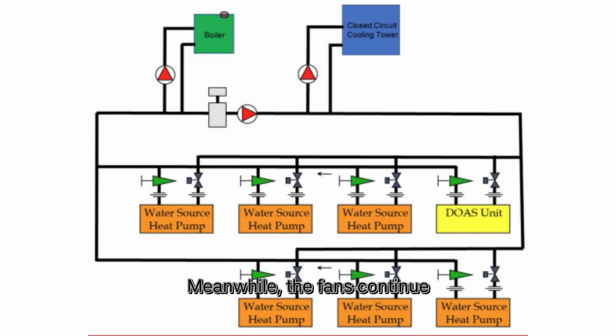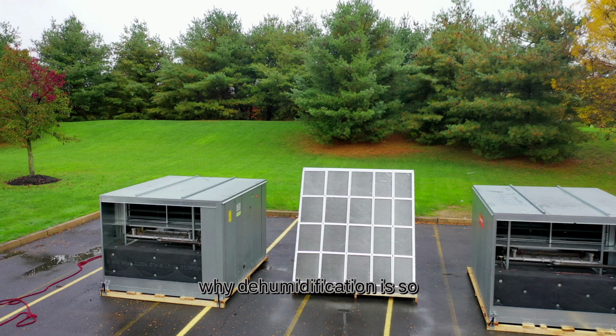Meanwhile, the fans continue to bring in more humid outdoor air, and the WSHP doesn't run long enough to remove that moisture. That's why incorporating a proper dehumidification strategy is critical in WSHP system design, especially in warm, humid climates like the Southeast United States. Now that we've covered why dehumidification is so important, let's look at the three main options for conditioning outdoor air in a WSHP system. Option 1.